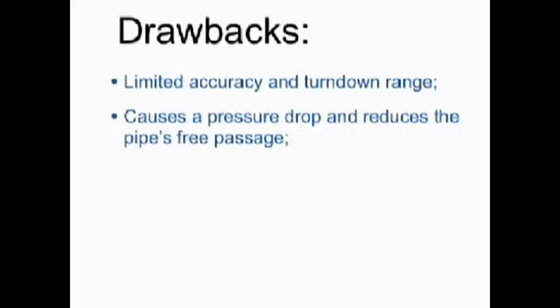Ultimately, accuracy and turndown are related to pressure drop. In other words, the more accuracy and range you need, the greater pressure drop you'll have to tolerate. The orifice is prone to wear. While there are no moving parts, the orifice itself is often a wear-prone point due to the high liquid velocity. If the orifice gradually enlarges with wear, the flow measurement will read low.